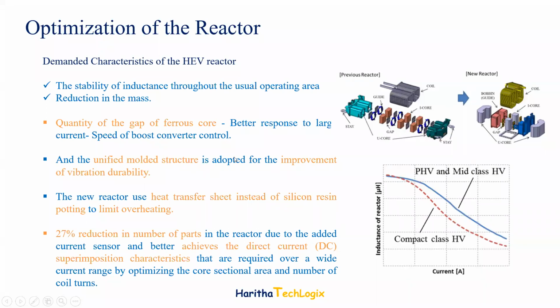They have created a unified molded structure compared to the previous design, and this has improved the vibration durability. It's not only about the current carrying capability of the reactor, but also its durability to withstand vibrations from the system. When the motor is working, and the inverter sits very close to the motor system, any vibration or noise from the motor might translate into the reactor, so the reactor needs enough strength for vibration durability.